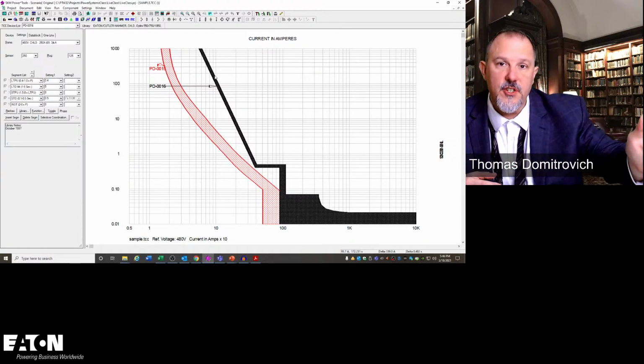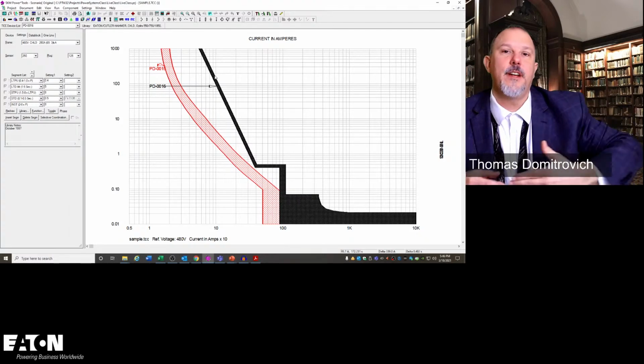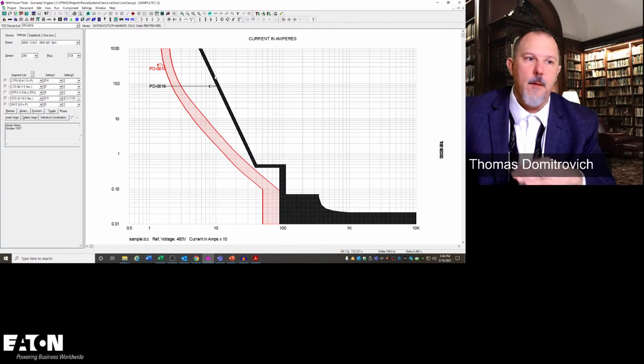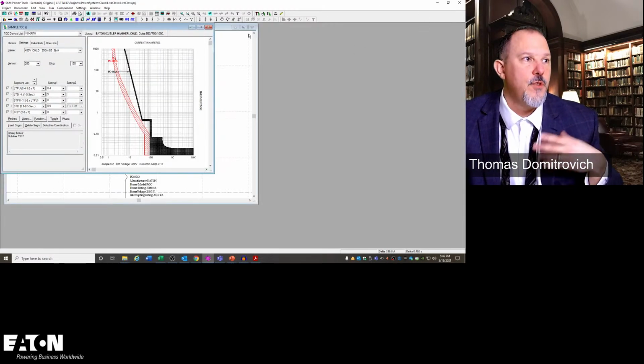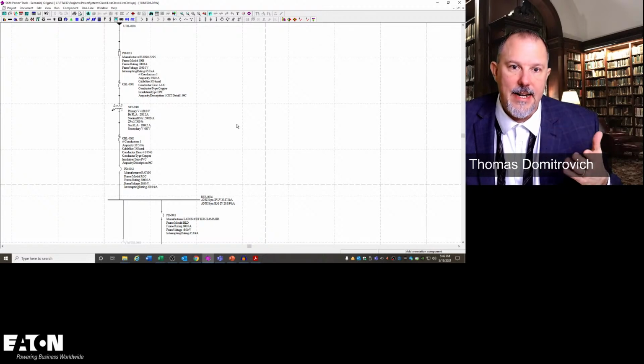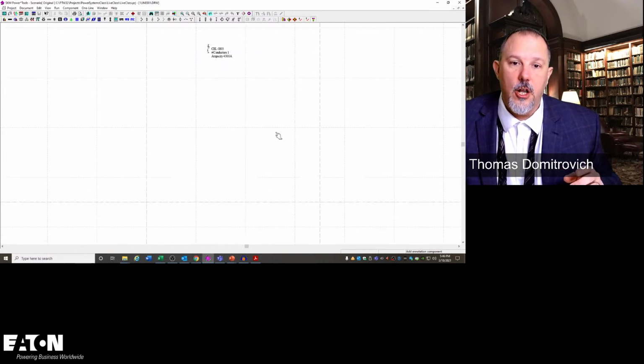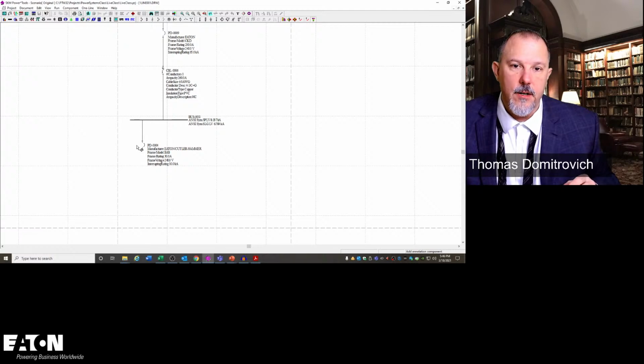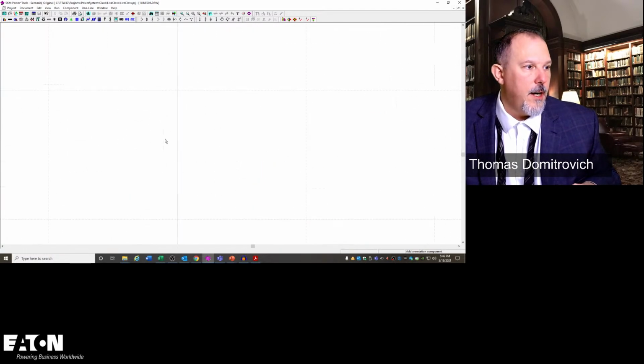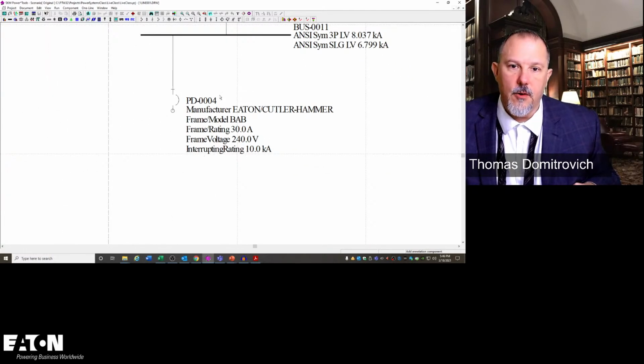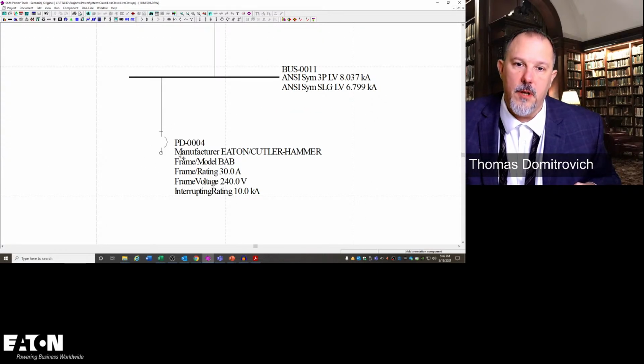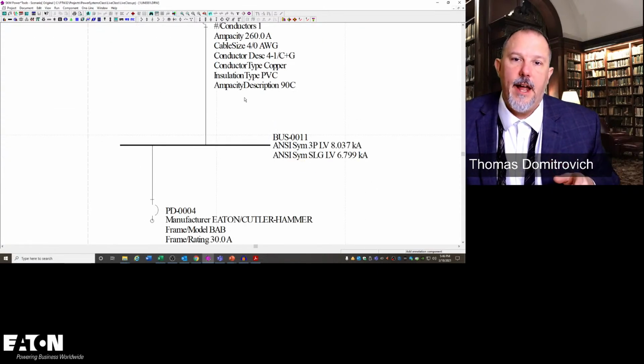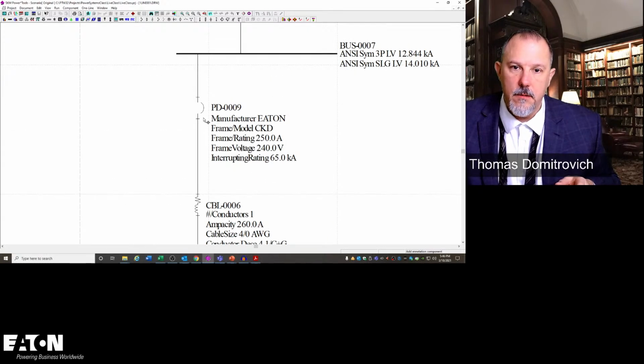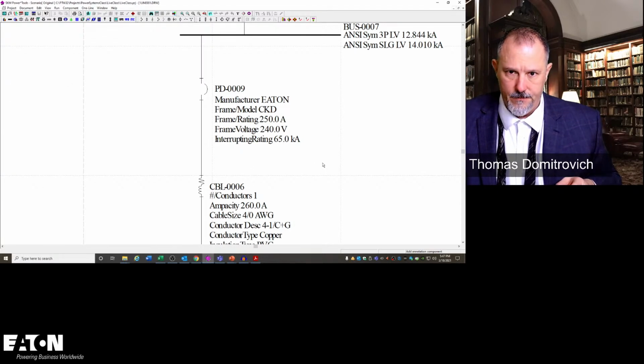So if those two breakers see 100 amps, the downstream breaker is going to clear the fault closest to the problem. The upstream breaker is not. And we typically work our way up from the load all the way up to the main. So if I looked at this one line diagram, I would start closest to the load. I'd go all the way down here to this circuit breaker, this 30 amp breaker right here, this BAB 30. I would plot that one first, and then I would plot the one upstream, and I would do an evaluation of those two breakers. My upstream breaker feeding this 250 amp.